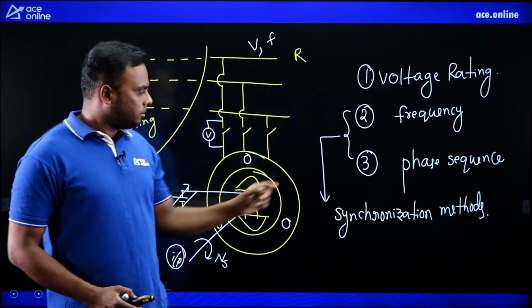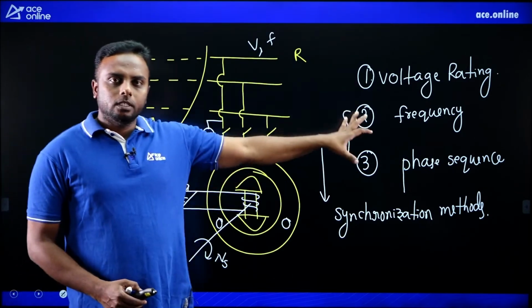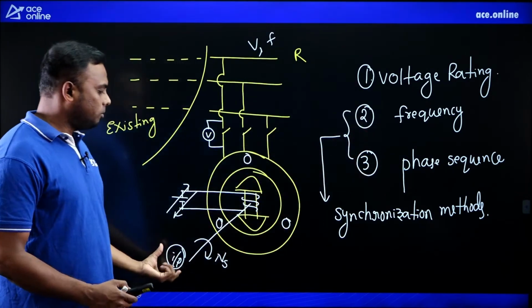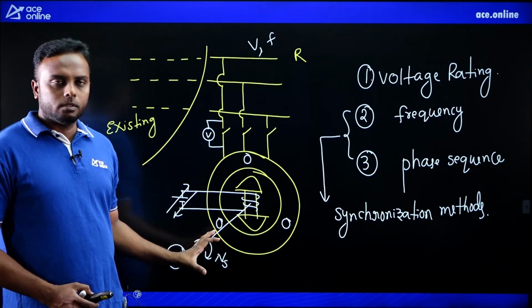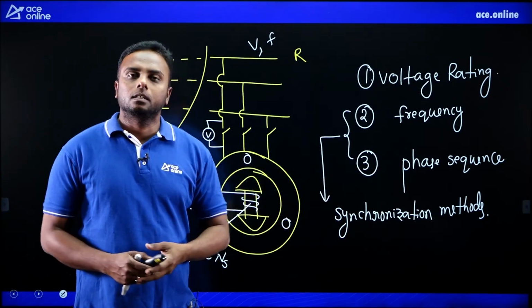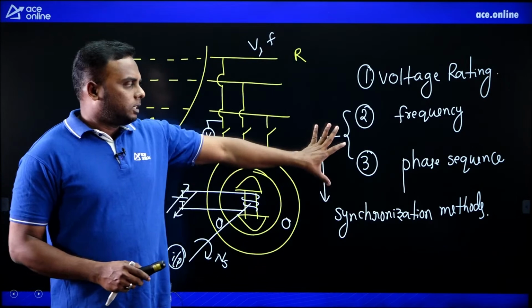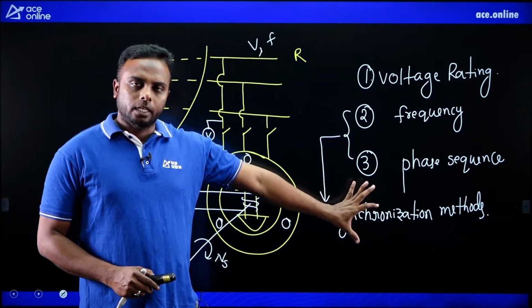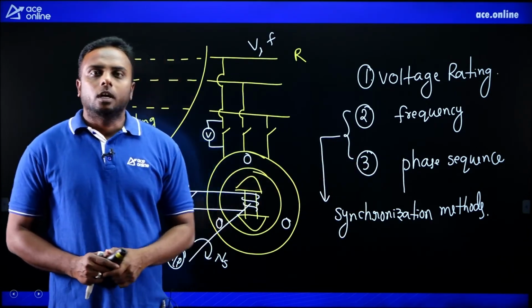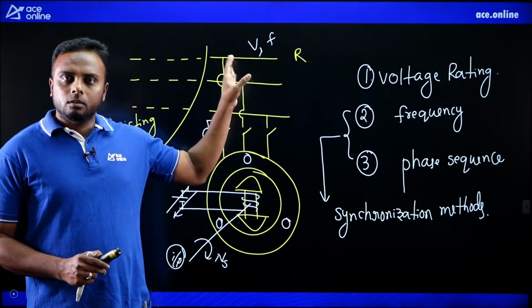Voltage rating can be adjusted by excitation, and frequency of the alternator can be adjusted by prime mover input or mechanical input. Next, the third one is phase sequence. So these are the conditions we verify by these methods. We will see the methods again. Now, suppose the phase sequence of the alternator is not the same as that of the bus bar sequence.